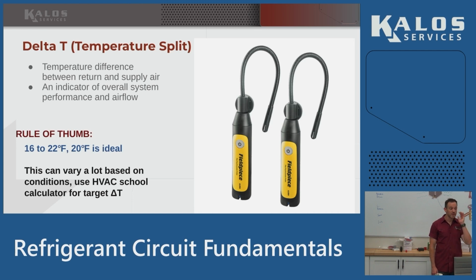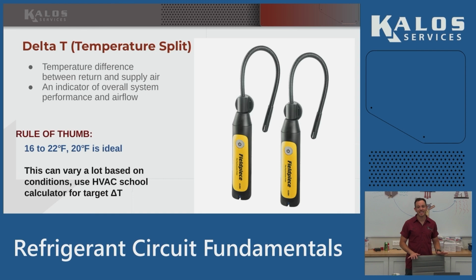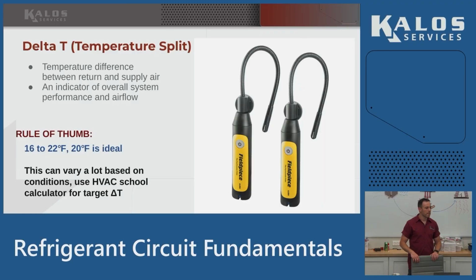So this is one of the 5 pillars. This is one of the things we'll look at that can help us determine if we have a low charge or an airflow problem. I think we touched on earlier, you don't want your temp split to be too high. If I have a high temp split, it's usually because my air is hanging out over my coil too long, which means I have an airflow problem. I'm either restricted, or I have a poor fan speed, or I have a dead blower motor, or something's letting my air get way too cold in there. My coil will freeze over eventually. And the other way, it just means I'm not cooling efficiently. With a high temp split, that's usually an airflow restriction.